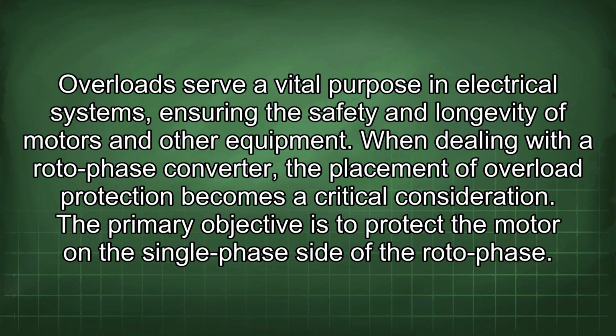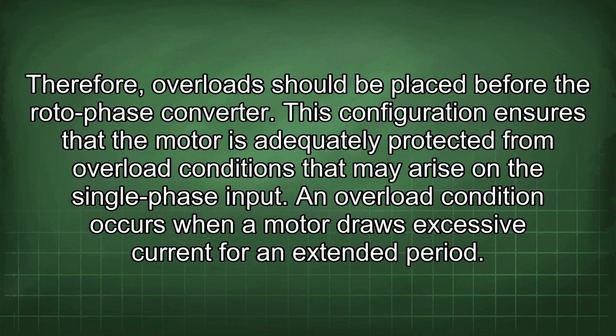Overloads serve a vital purpose in electrical systems, ensuring the safety and longevity of motors and other equipment. When dealing with a roto-phase converter, the placement of overload protection becomes a critical consideration. The primary objective is to protect the motor on the single-phase side of the roto-phase. Therefore, overload should be placed before the roto-phase converter. This configuration ensures that the motor is adequately protected from overload conditions that may arise in the single-phase input.